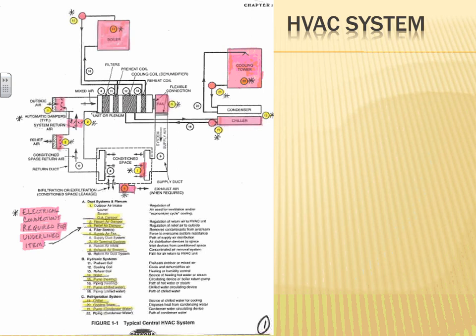Ideally. Okay. And this is meant for explanation too. We don't have to go deep into all this stuff, but it's really nice to know where the points of connection are. Because when it comes to electrical and mechanical, we overlap a lot in a lot of areas, and it's really nice to know where the electrical contractor's responsibility stops versus the mechanical contractor's, as well as the engineering side of it. You guys are in-house, so you don't fight a lot, but in the field, the mechanical and electrical contractors have to be coordinated on who's going to be pulling the EMT conduits to this Class 2 circuit that's going to be controlling this. Who's going to put the conduits, who's going to put the wire, who's going to wire it, who's going to install it, and so forth.